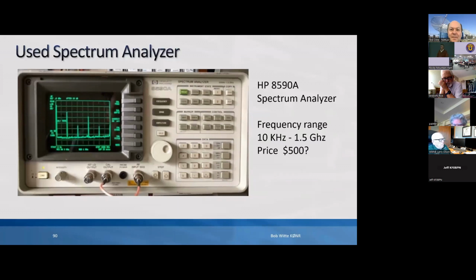Hey, Bob. Yeah, there's a lot to love about that old stuff. I think one thing to point out with the spectrum analyzer is it does have a broad frequency range. So it's got a real wide receiver, and you've got to be careful with the signals that you put in there. You may want to use a filter. Otherwise, you may be seeing intermod and stuff generated within the instrument from overload. Yeah, that's a good point. Basically, this is an imperfect device, same as all these spectrum analyzers we've been talking about. One phenomenon is if you drive it too hard on the input, you can create distortion in the front end of the analyzer, and you start thinking, oh, that's in my signal, it's in my transmitter. It may not really be there, right? So you always have to be careful.